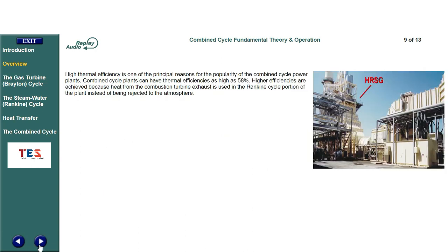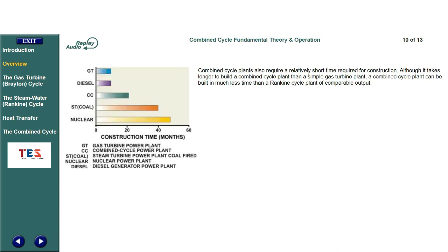High thermal efficiency is one of the principal reasons for the popularity of combined cycle power plants. Combined cycle plants can have thermal efficiencies as high as 58%. Higher efficiencies are achieved because heat from the combustion turbine exhaust is used in the Rankine cycle portion of the plant instead of being rejected to the atmosphere. Combined cycle plants also require a relatively short time for construction. Although it takes longer to build a combined cycle plant than a simple gas turbine plant, a combined cycle plant can be built in much less time than a Rankine cycle plant of comparable output.